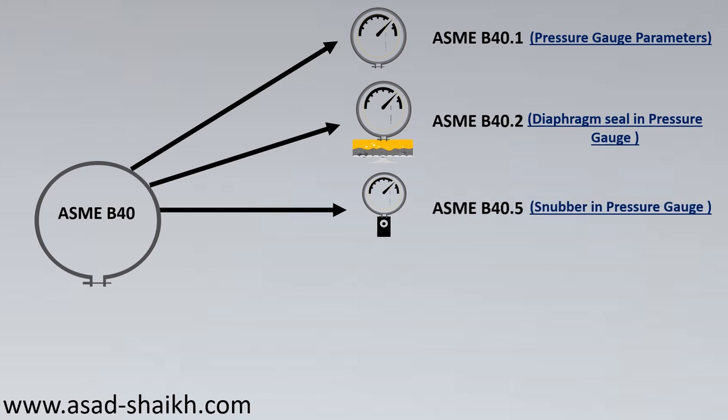The third part, ASME B40.5, deals with snubbers and pressure gauges. A snubber is a small device that can protect a pressure gauge in the long run — a lot of pressure gauge failures are attributed to improper snubber installation. As a rule of thumb, a snubber is used in high-pulsation applications such as pump discharge. Snubbers come in various types, and this standard covers which type to use and when.